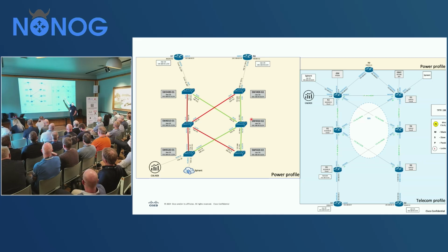Because that Grandmaster is then inserting both PTP and SyncE into the network, and we are transmitting it through the wide area network. 8275.1 is a link-by-link protocol. It's master-slave, master-slave, master-slave through the entire network before you then hit the substation at the bottom.